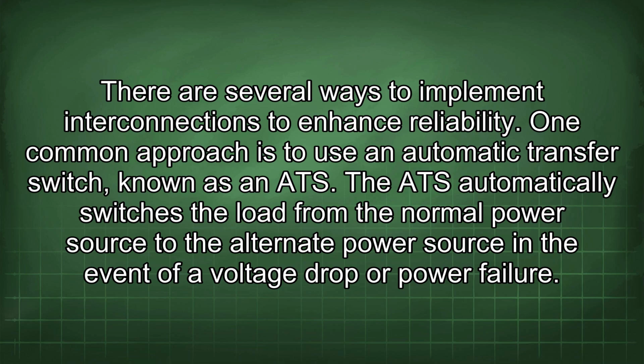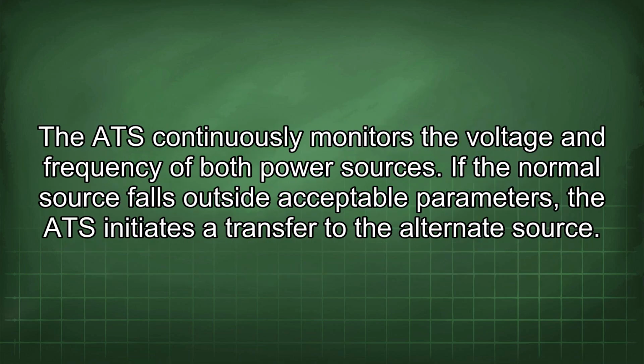There are several ways to implement interconnections to enhance reliability. One common approach is to use an automatic transfer switch, known as an ATS. The ATS automatically switches the load from the normal power source to the alternate power source in the event of a voltage drop or power failure. The ATS continuously monitors the voltage and frequency of both power sources. If the normal source falls outside acceptable parameters, the ATS initiates a transfer to the alternate source.